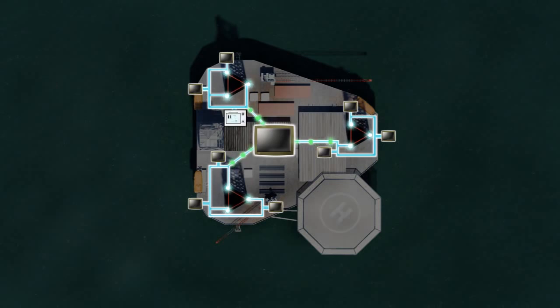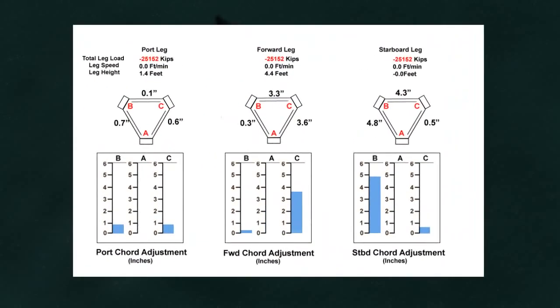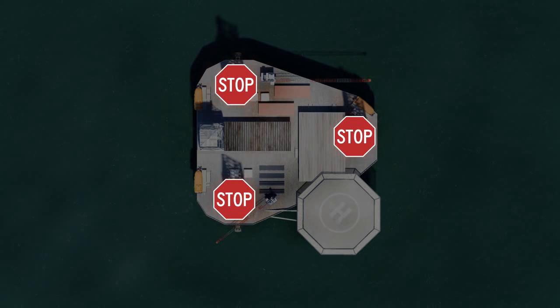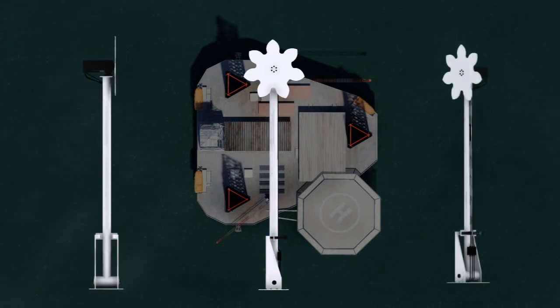Data reporting includes leg length, RPD error indication and alarm, trending and historical logging, as well as the ability to enter comments and notations. The RPD M1000 also provides the operator with a corrective action to be taken to solve problems identified by the system. As a leg can be seriously damaged in 10 seconds if one of the chords should jam in the hull, RPD M1000's fail-safe monitor will automatically shut down the jack-up process if the operator does not respond fast enough to a warning signal.